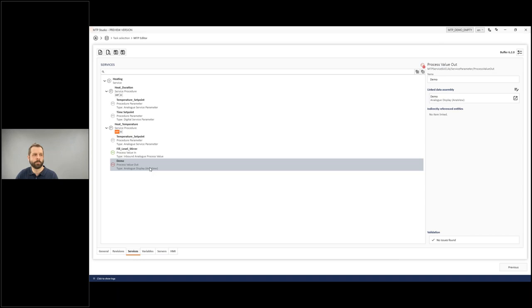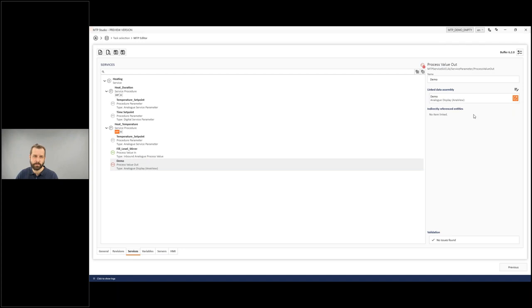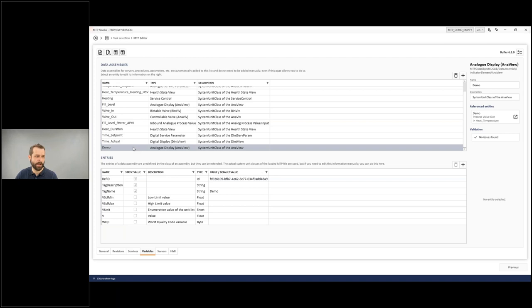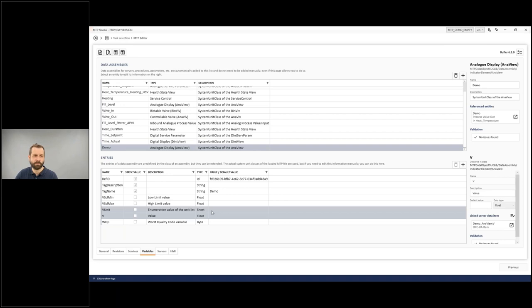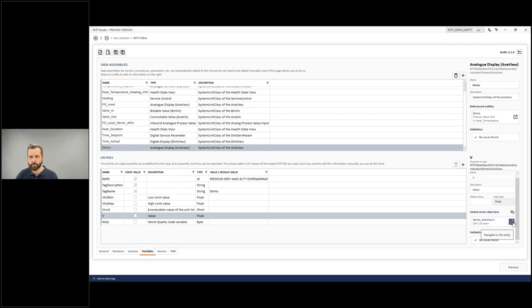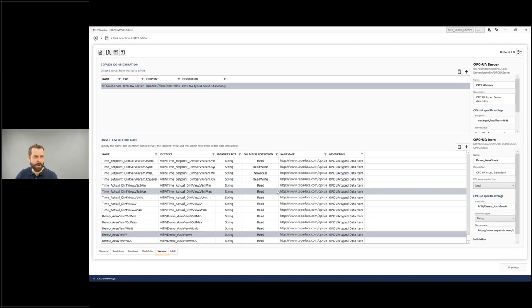The new parameter appears with its data type. This Analog Display — or AnaView — is a data assembly. Data assemblies are at the core of MTP, following the specification, and everything you see is linked to such a data assembly. They are required to describe what a parameter is doing. You can edit them via the Variables tab, or use the navigation feature — since everything is linked in MTP, the application switches tabs and preselects the relevant data assembly.